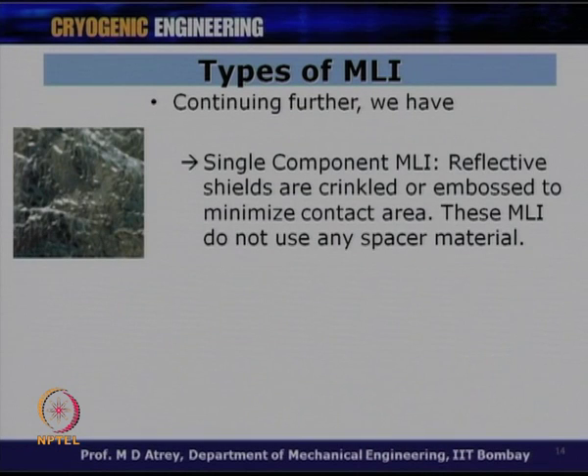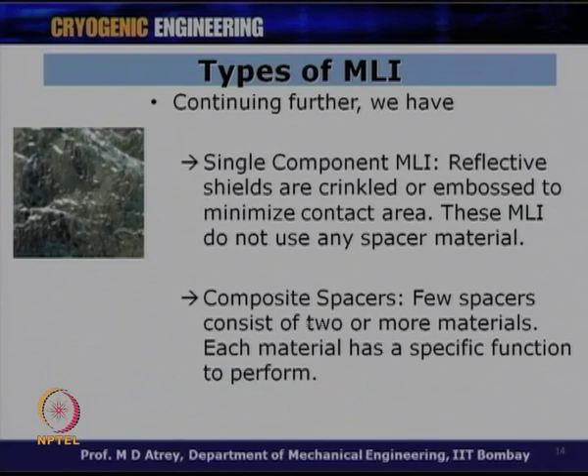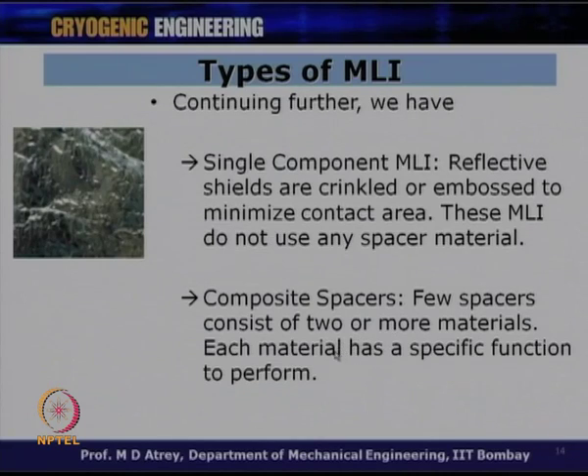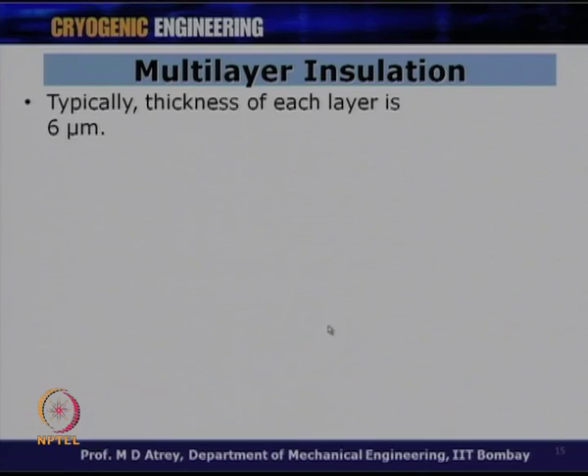Single component MLI, also called crinkled multilayer insulation, uses point contact rather than area contact to minimize solid conduction. Composite spacers are also possible, consisting of two or more materials each with a specific function. Typically, the thickness of each layer is around 6 micrometers. Residual gas conduction inside the insulation depends on residual pressure, and in good vacuum this can be considered zero.